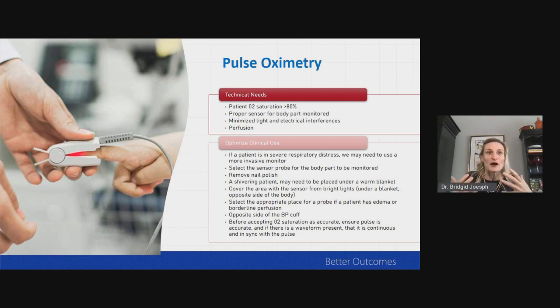The accuracy of the pulse ox is plus or minus 2% on patients that have a reading anywhere from 80% to 100%. If the pulse ox is reading less than 80%, the accuracy is pretty low. It's no longer really accurate.